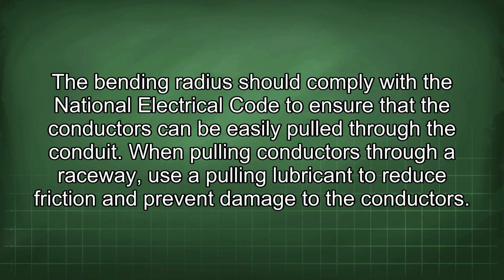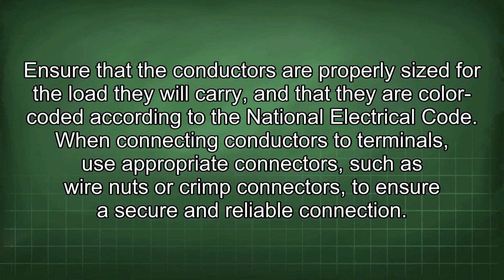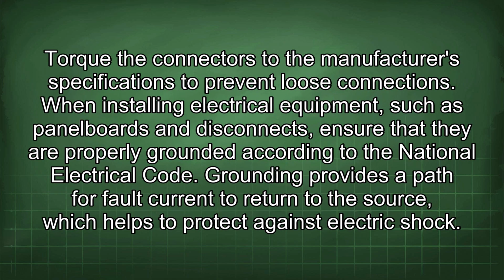When pulling conductors through a raceway, use a pulling lubricant to reduce friction and prevent damage to the conductors. Ensure that the conductors are properly sized for the load they will carry and that they are color-coded according to the National Electrical Code. When connecting conductors to terminals, use appropriate connectors such as wire nuts or crimp connectors to ensure secure and reliable connection. Torque the connectors to the manufacturer's specifications to prevent loose connections.